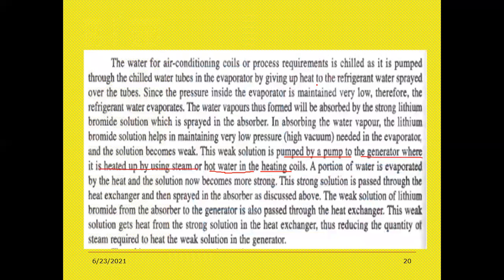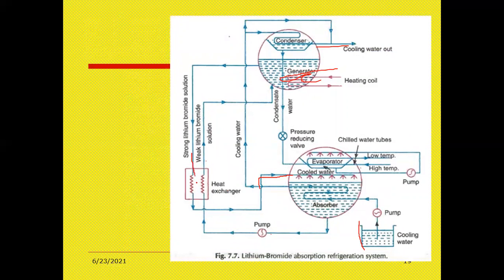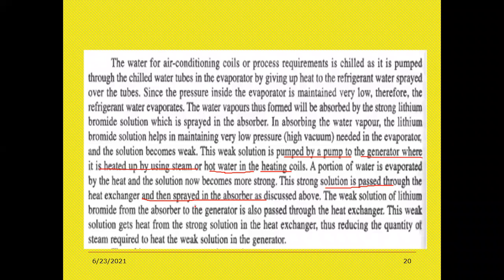A portion of the water is evaporated by the heat and the solution now becomes much stronger. This strong solution is passed through the heat exchanger and then sprayed into the absorber, as discussed above. The weak solution of lithium bromide going from the absorber to the generator is also passed through the heat exchanger. This weak solution gets heat from the strong solution in the heat exchanger, thus reducing the quantity of steam required to heat the weak solution in the generator.